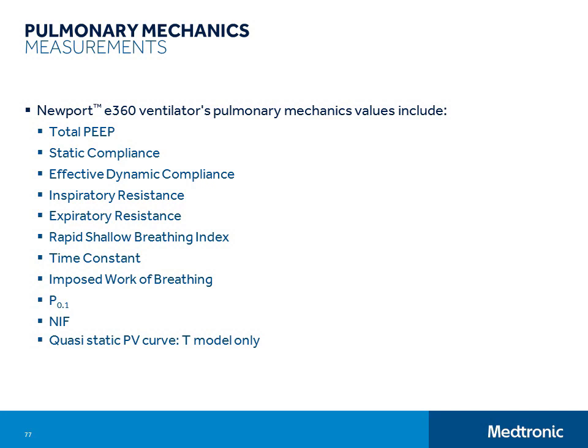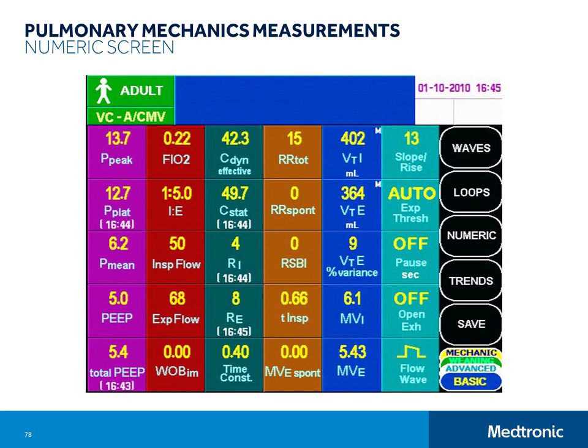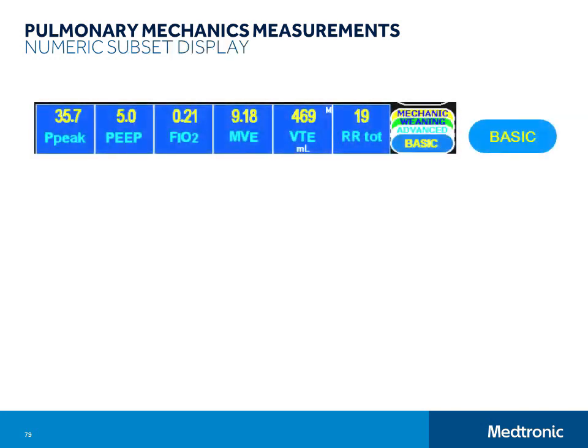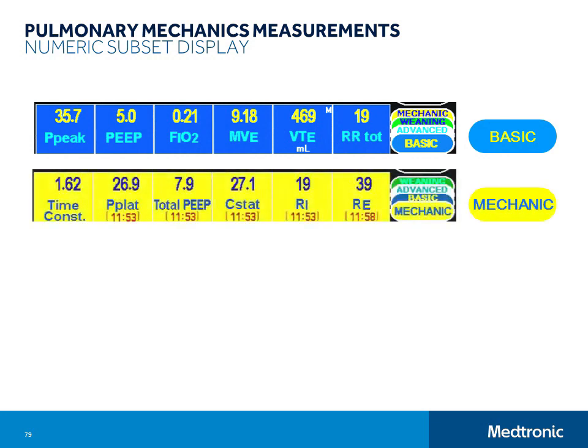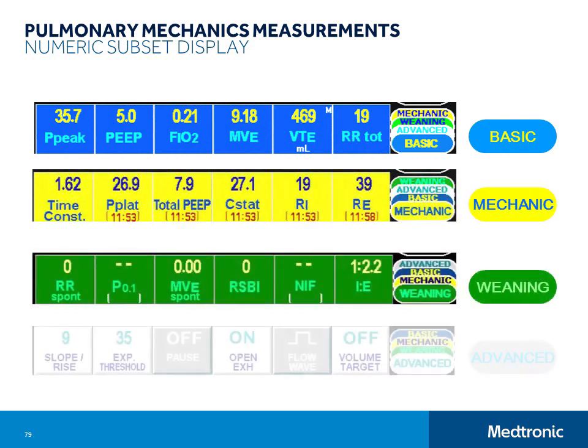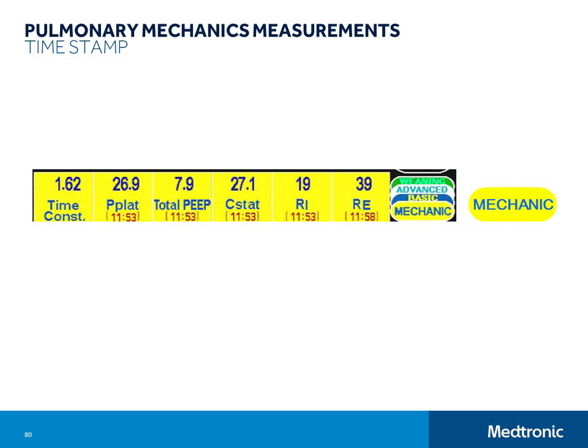The mechanics values that are based on the inspiratory and expiratory hold maneuvers are displayed with a military timestamp beneath the numeric value. The value is retained for up to 24 hours or until they are replaced with a new value, whichever comes first. When you perform a hold maneuver, make certain that the patient's respiratory drive is suppressed and that there are no active breathing efforts. If the patient is actively breathing during these maneuvers, the measured values will be skewed. Here is the process for doing the end expiratory and end inspiratory hold maneuvers.